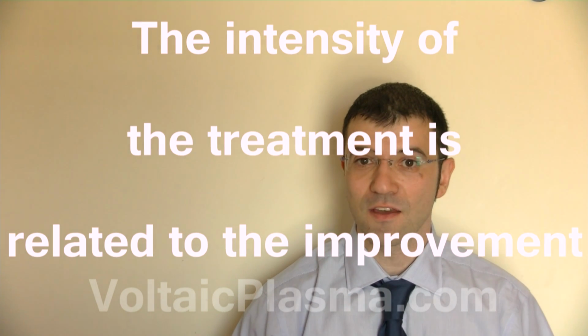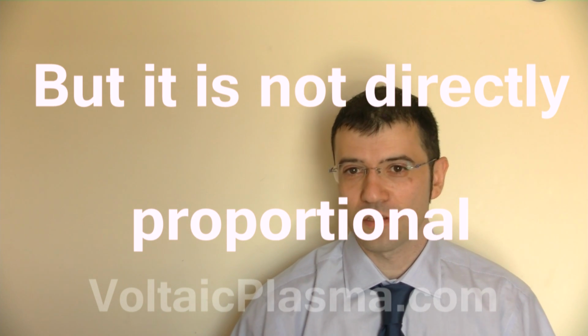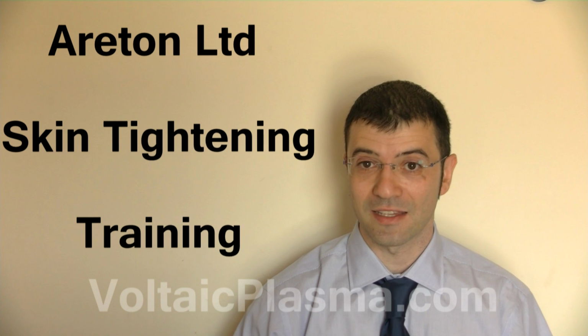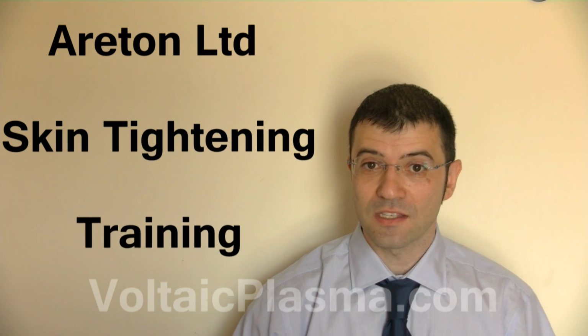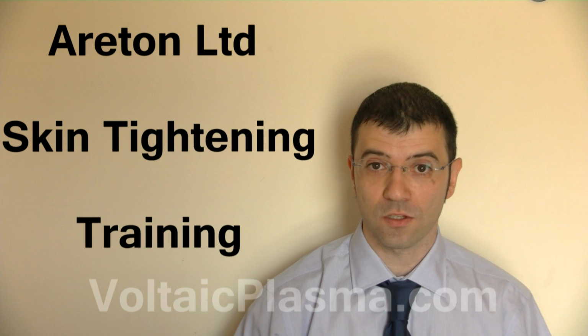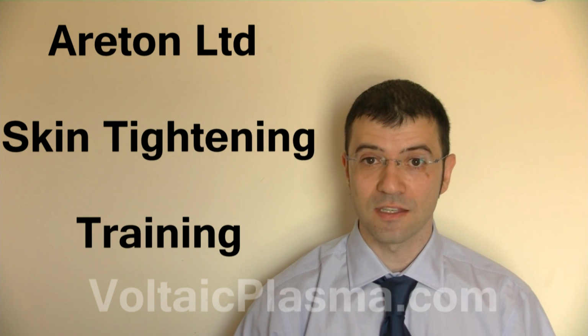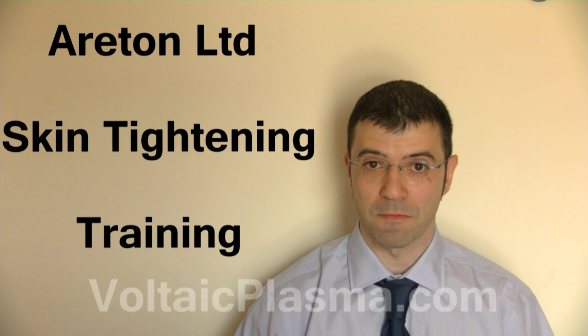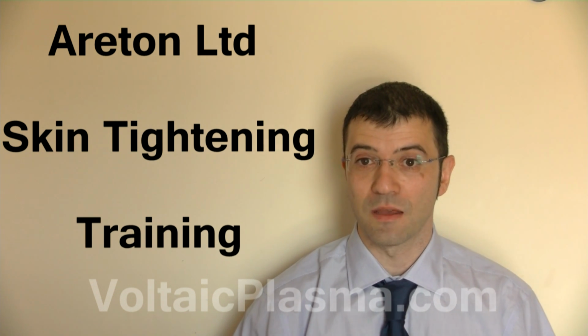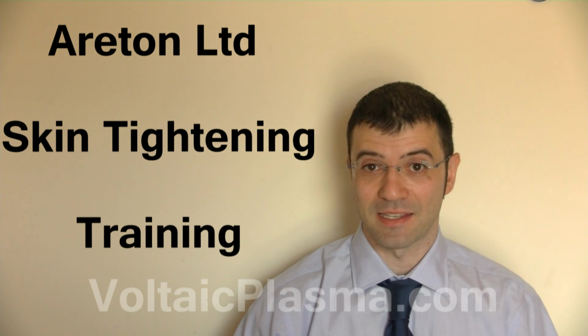In other words, the degree of improvement is not directly proportional to the aggressiveness or intensity of the treatment. To explain this important concept, if for example over the course of one treatment the duration of the arc at each point is half a second, this leads to a slightly enhanced improvement compared to a treatment where the duration of the arc is only a quarter of a second, all the other factors like power level, area covered, and distance between carbonization spots remaining the same. Doubling the duration of the arc application does not necessarily lead to an improvement which is twice as good. It would only be slightly better.